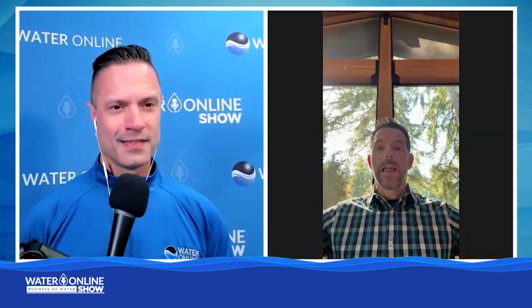The second is the external ring header. So you can picture that. It's just basically 8 holes punched in the bottom of the lower shell of the vessel with a collection ring pipe below it. And then the third is going to be the header lateral system. So you've got a common influent coming in the lower side shell of the vessel, and then it's got these laterals, or you can kind of picture them as spider legs or octopus tentacles that spread out over the bottom to collect the water. And all these underdrains basically are attempting to accomplish the same thing, which is keep the media in the vessel and let the water go through. So those are the three main ways to kind of map it out.